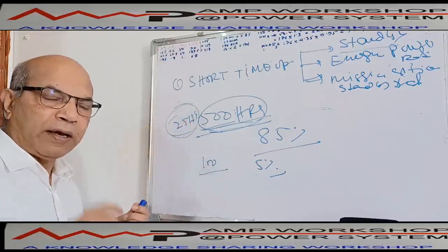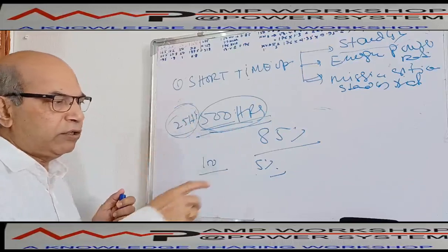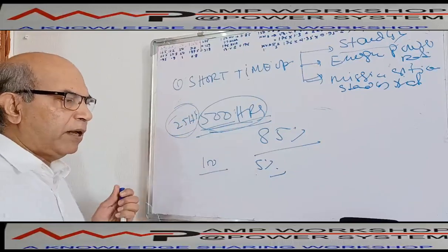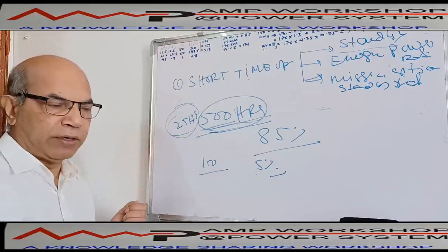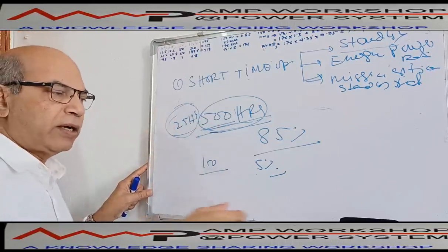And another point is, this 25 hours cannot be continuous. It is only 5% of the year, but every 12 hours you can load by 1 hour. So this is the case of the mission critical standby generator rating.